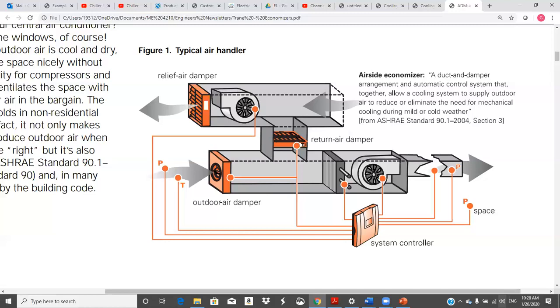Well, that's what would happen if we didn't have this fan, and this would be called a relief fan. And so then it takes that return air and it just blows it outside. Now on small systems, this one fan may be enough. And you can do things I call gravity dampers that are just above the drop ceiling. You put a little pressure on the inside and it's enough to force them open, and the air just flows out of the building all around the exterior shell. That's a cheap way of relieving the pressure in the building when you go on. This is called economizer cycle. This is called an airside economizer. Okay?